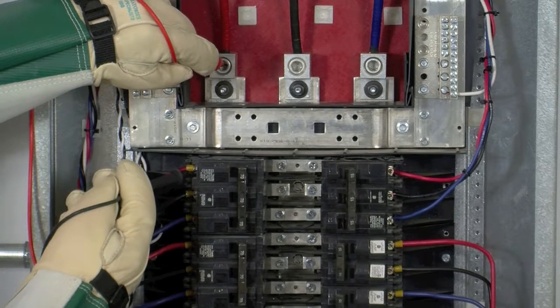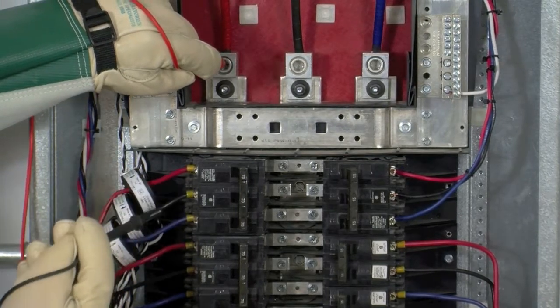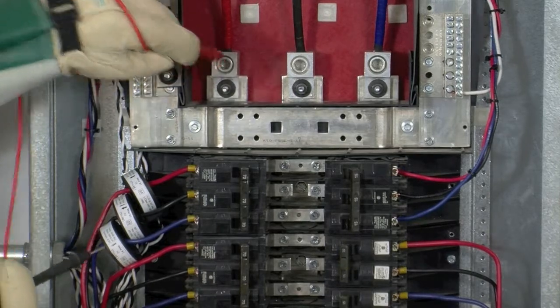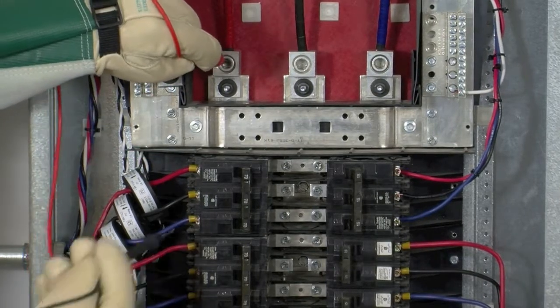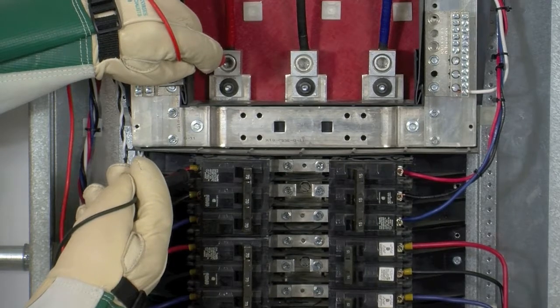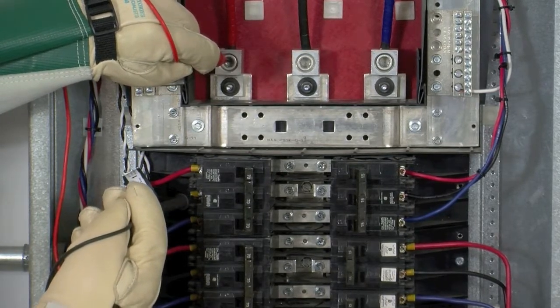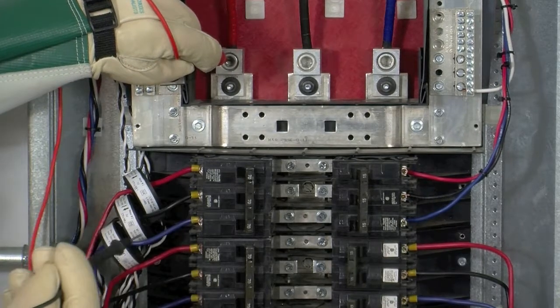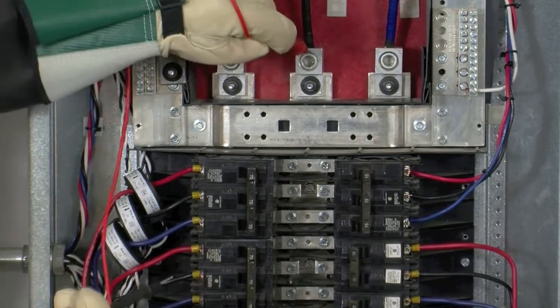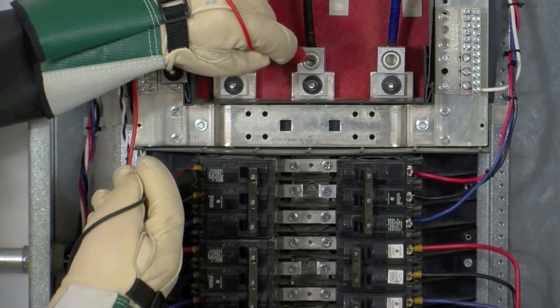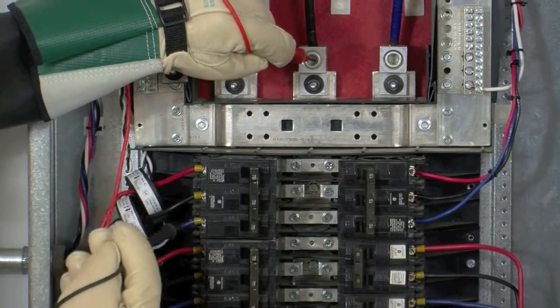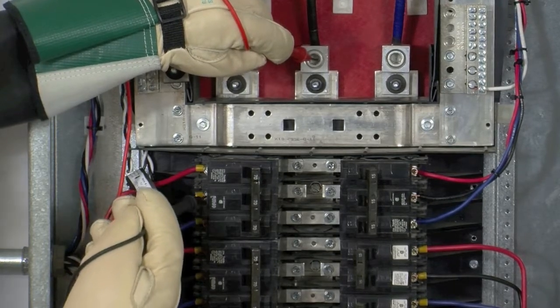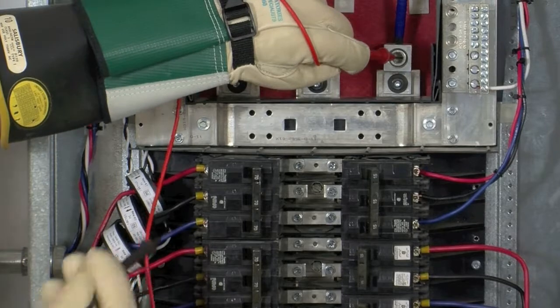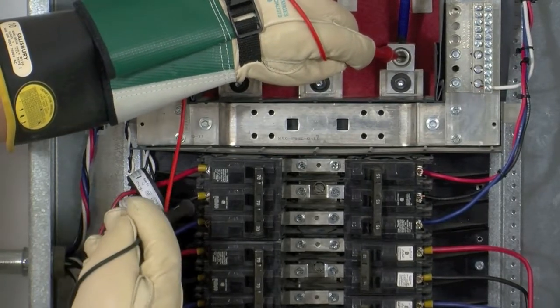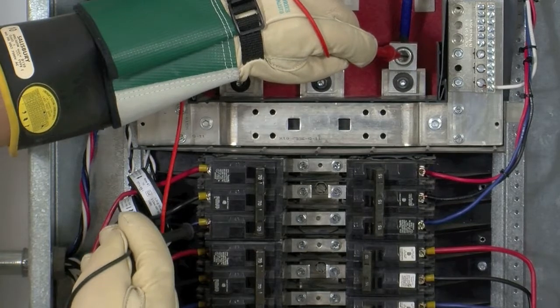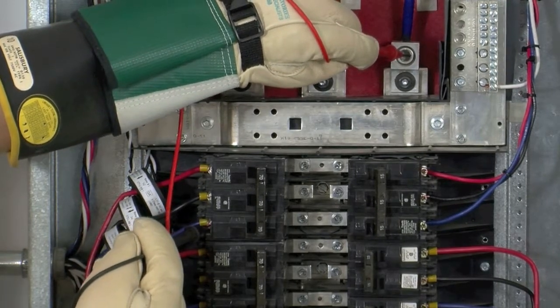If we have 0 volts difference, we know that this is phase A. If it was any other phase, there'd be a voltage difference of roughly 208 volts in a panel like this. So here we have 0 volt difference, so we know it's phase A. Here we have 208 volts, and here we have 208 volts. So we're going to repeat that test for phase B. Here we have 208, here we have 0 volts, and here we have 208. So we know that the middle pole is phase B. Moving on to C. Here we have 208, here we have 208, and here we have 0 volts. So we know that the bottom pole is phase C.